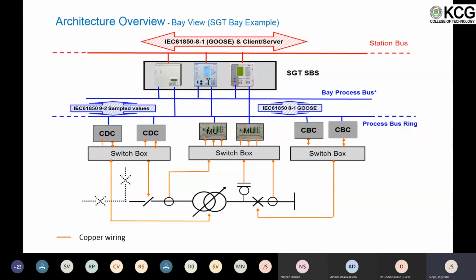And with the switch box concept, you don't need an outage of the whole primary side. There are spare things available. You connect to the spare side of the switch box and put the new device, test it. Once you start communicating with the station system, you can remove the older device. Very simple thing to do. So that's the purpose of switch boxes.